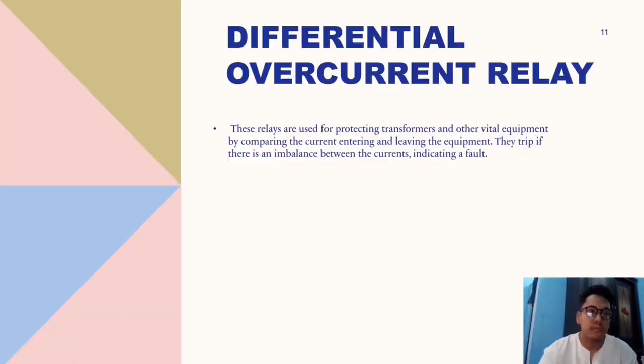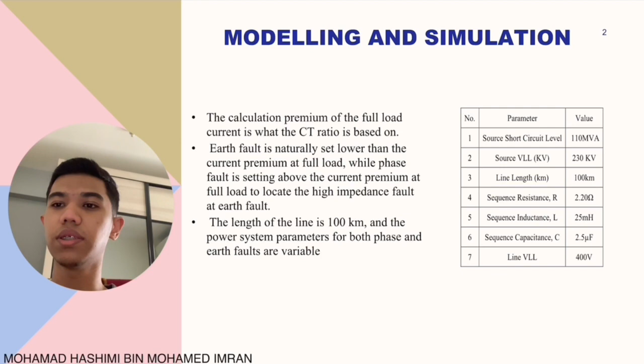Today I want to present about the design and implement of overcurrent relay to protect the transmission line. Okay, we start with modeling and simulation. For modeling and simulation, the calculation of the full load current is what the CT ratio is based on. On the table is the parameter and the value used for design. The earth fault is normally set lower than the current at full load, while phase fault is set above the current at full load to locate the high impedance fault at earth fault. The length of the line is 100 km, and the power system parameter for both phase and earth fault are variable.